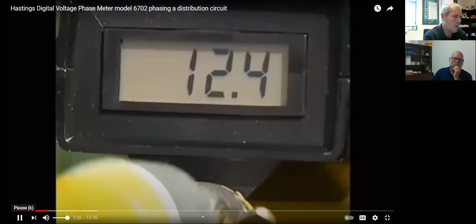Road to field, I'm seeing 12.4, which is phase-to-phase voltage, so that's showing good. Just for security, let's go to non-metered in for that center phase out on top, and I'll go to the field phase. I'm seeing 12.5, so that's a phase-to-phase voltage. You ready to check the bottom side of this cutout?